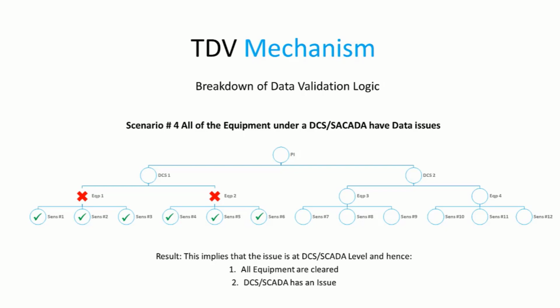Talking about the mechanism, if all the equipment under the DCS or the SCADA have data issues, as we see here, if both pieces of equipment under the DCS1 level are having data issues, that implies the issue is not at the equipment level, it is at the DCS level. So this is how we track where the location is under each scenario.